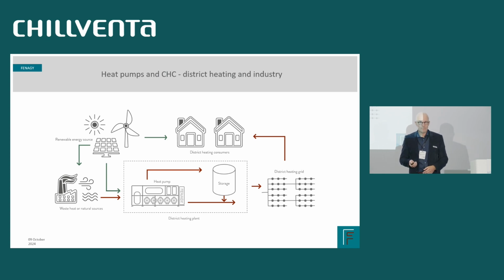So, power from here into the heat pump. We heat the water that we need to heat on the user side. But of course, a heat pump needs an energy source, a heat source. And we basically don't care where it's coming from. It could be waste heat, which is a good idea if there is any waste heat, but it could also be a natural source. And a natural source is what we have available in nature. It could be groundwater, it could be air, it could be the sea, whatever is available.